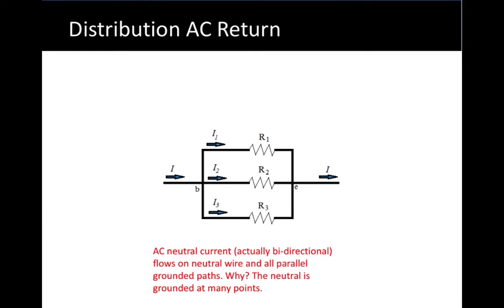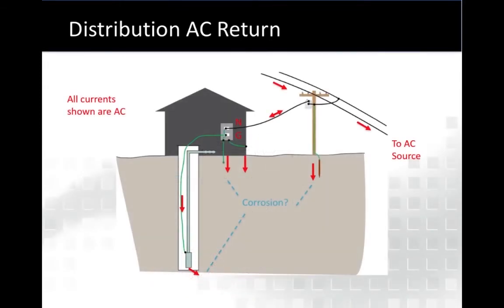So there could be an effect on a water well system, and this indeed has occurred, where there's premature death of a submersible pump and the bowl or the column because of corrosion. But it's probably a little bit different effect. Any of these systems could suffer corrosion, but chances are the surface grounding systems really are not going to have any notable effect for corrosion. But water wells themselves have had their pumps damaged.